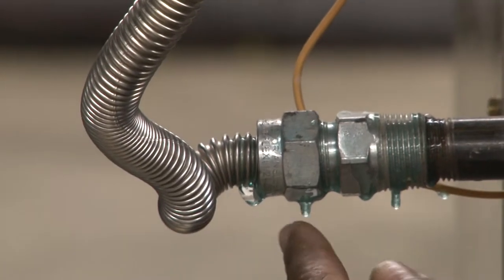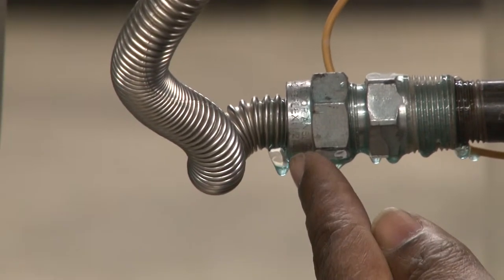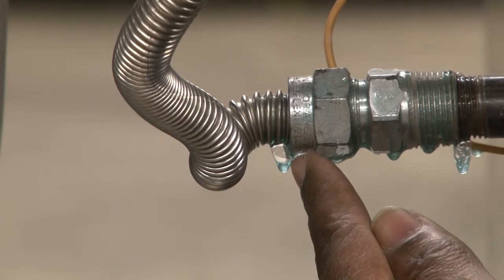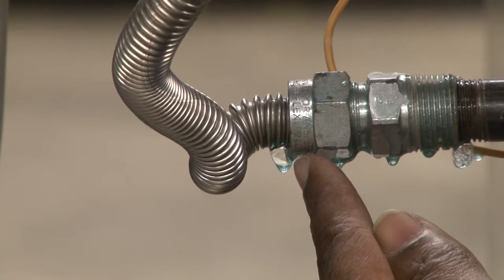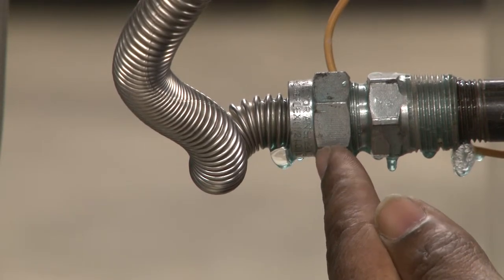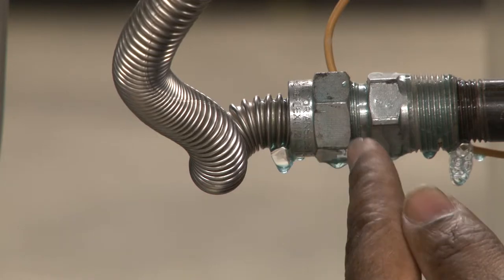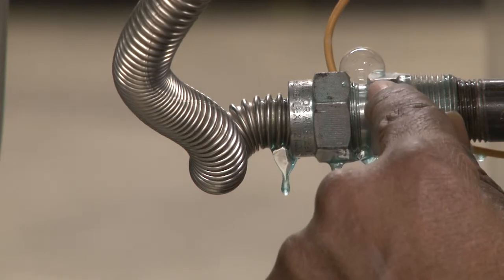And if you zoom in, you can see that the leak is coming from this fitting on the left side. The leak detector picked up the general area where it's coming from. There's another leak forming there.